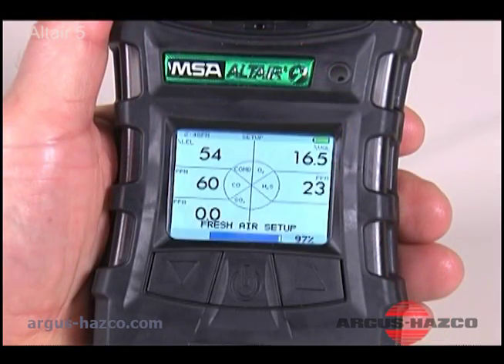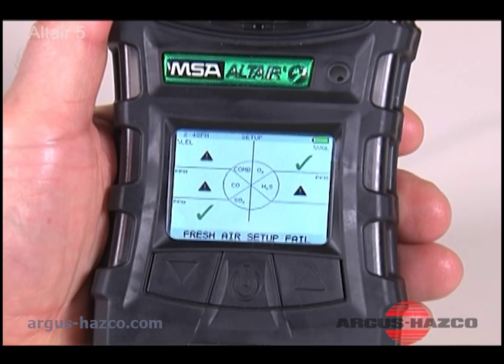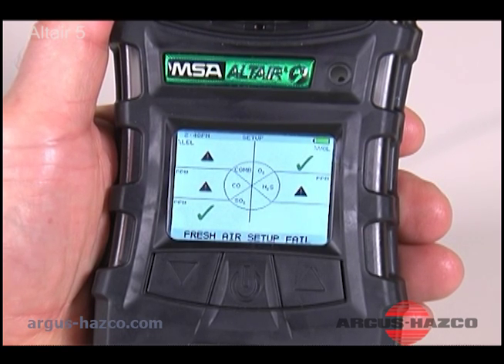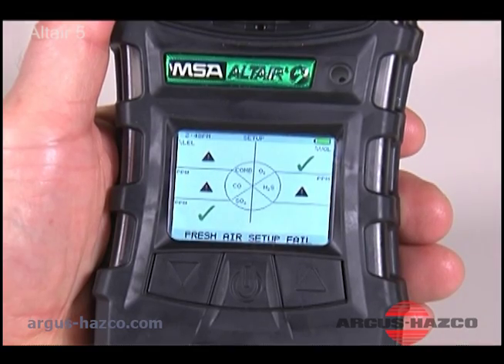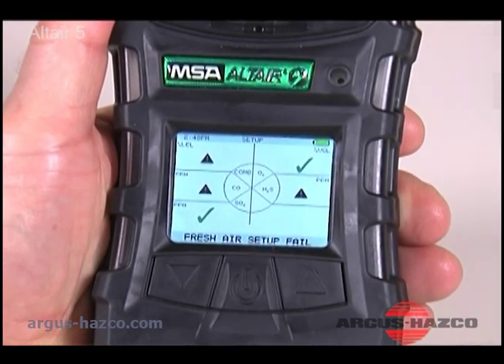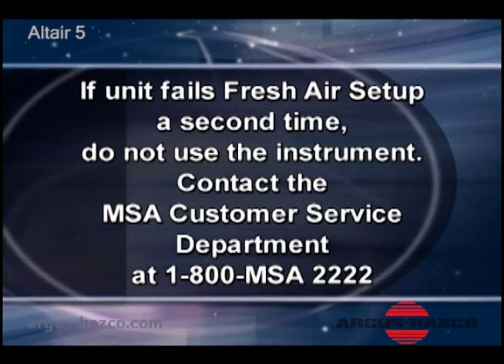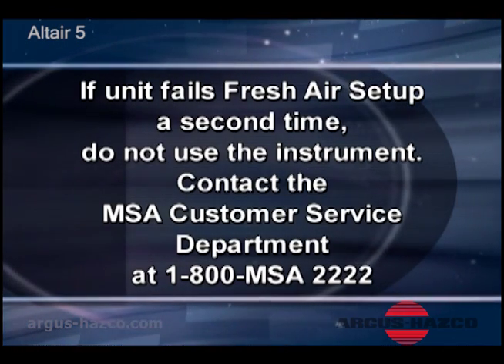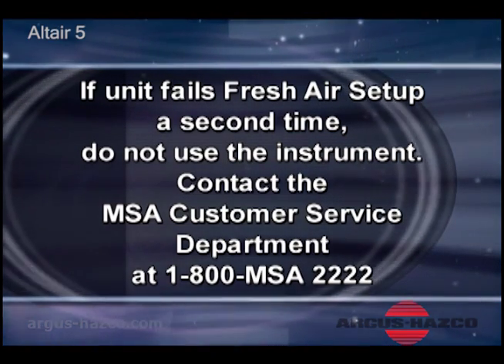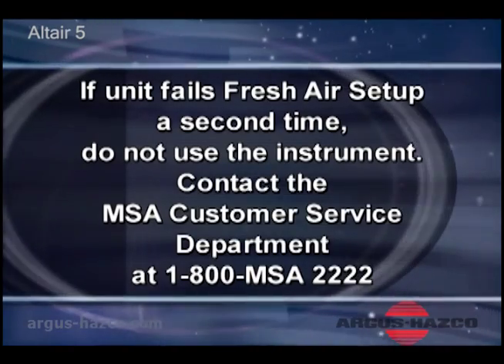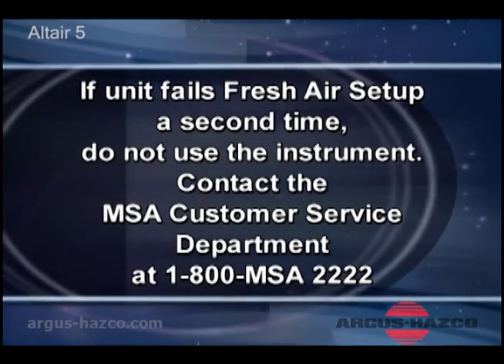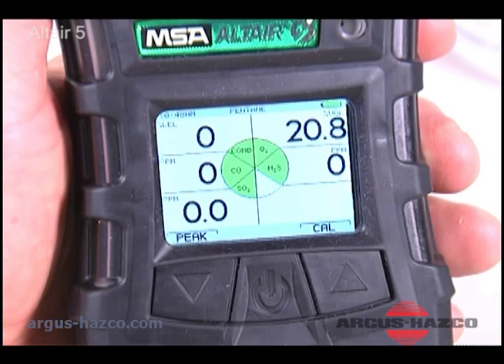If a sensor 0 point falls outside the preset limits, the display identifies the faulty sensor. If the instrument fails a fresh air setup, repeat the process. If it fails a second time, do not use the instrument. Contact the MSA Customer Service Department at 1-800-MSA-2222.